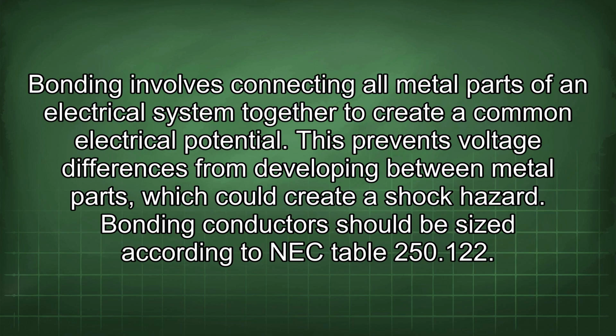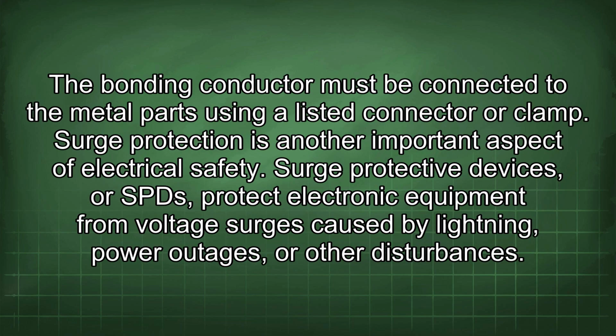Bonding involves connecting all metal parts of an electrical system together to create a common electrical potential. This prevents voltage differences from developing between metal parts, which could create a shock hazard. Bonding conductors should be sized according to NEC Table 250.122. The bonding conductor must be connected to the metal parts using a listed connector or clamp.